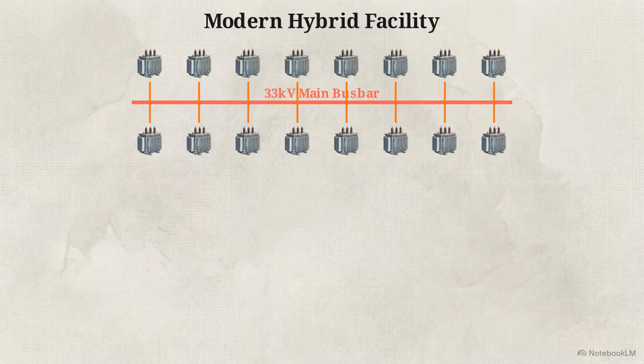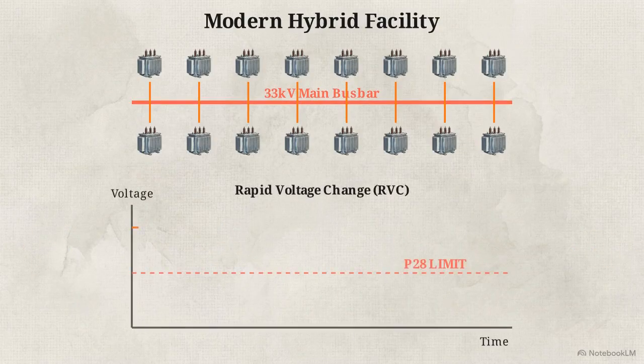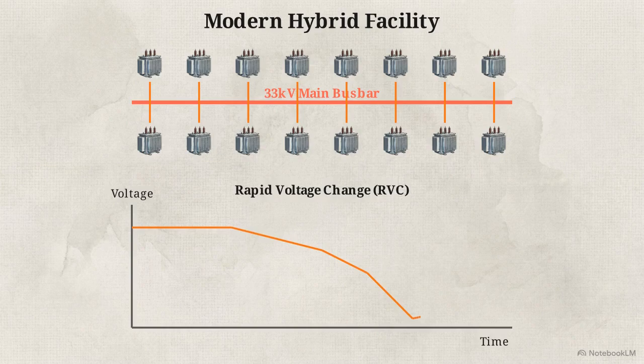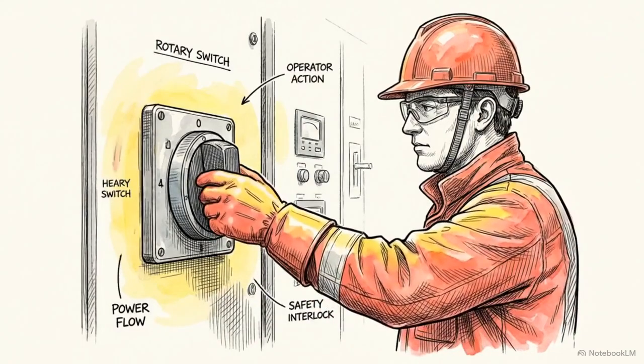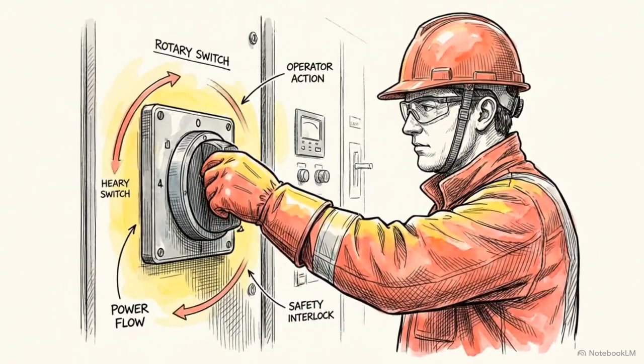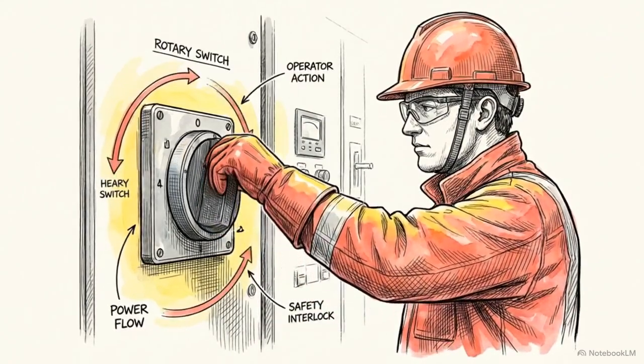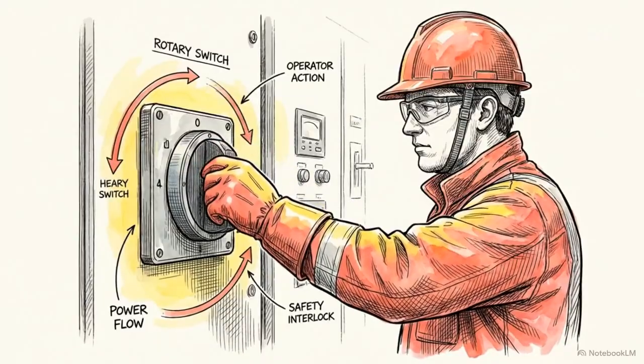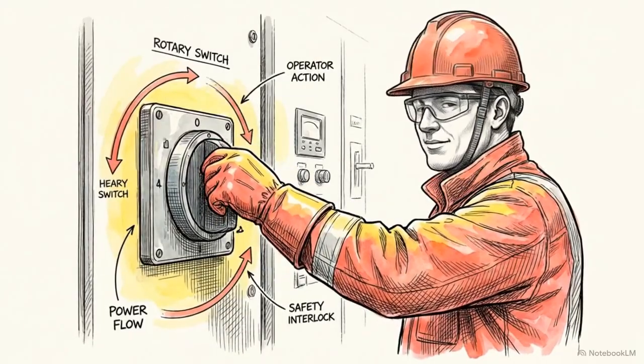Energizing all 16 transformers simultaneously compounds the probabilistic risk of hitting maximum inrush. Doing so guarantees a massive voltage dip that completely breaches the P28 limits. The forced alternative is sequential energization. Operators must close the breakers one by one, managing the inrush of each individual transformer.